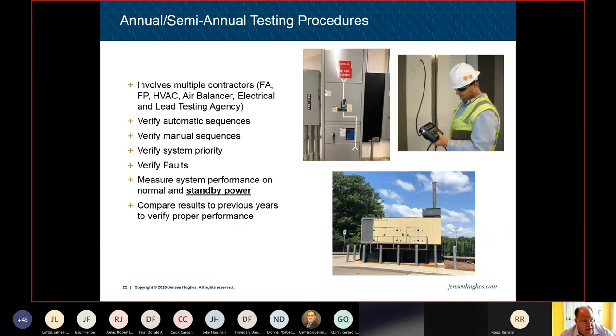In the bottom right picture, you see an outside emergency generator at one of the buildings that needs to automatically turn on. We do a number of these tests, but the big test that we normally do is we take out all the bypasses on the fire alarm system. The whole building's in its normal state, outside of having the master box or the central station offline, because you obviously don't want the fire department rolling.